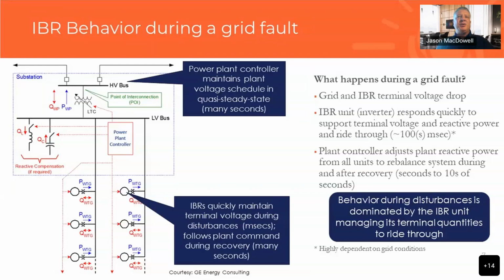They have very fast controls that operate on the order of milliseconds. I have a callout here of a total quickly responding to an event within 100 milliseconds. That's debatable. Is it total response? Is it settling time? That's not the point I'm trying to make. The point is that it's fast, much faster than the plant level control is, to keep the voltage constant, stable and regulated at the point of connection. The plant level controls will take over and regulate the quasi-steady state at the point of connection on the order of seconds to tens of seconds due to normal fluctuations of the grid.